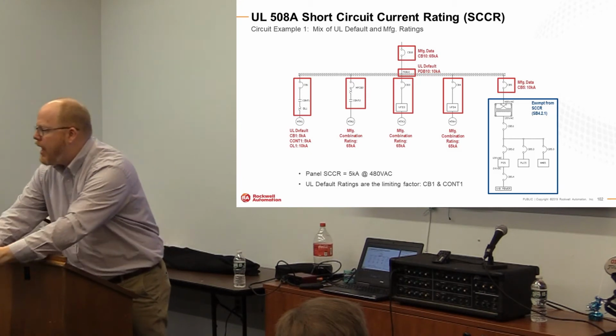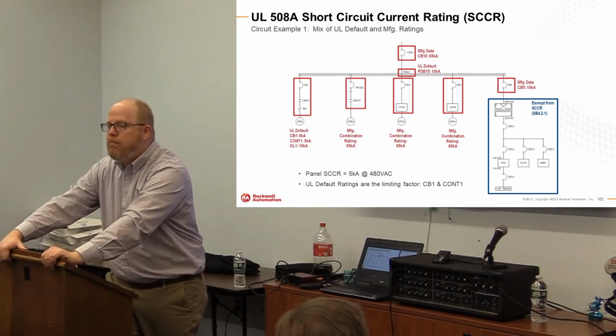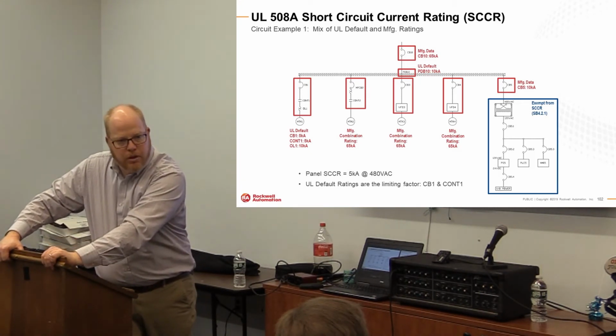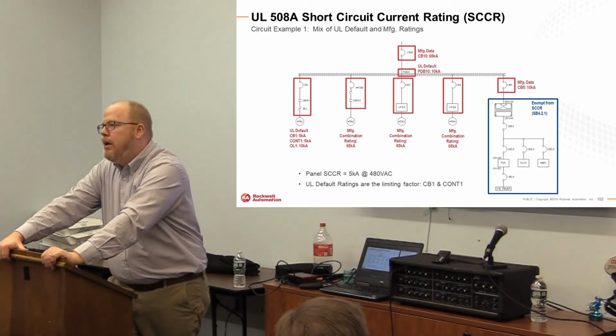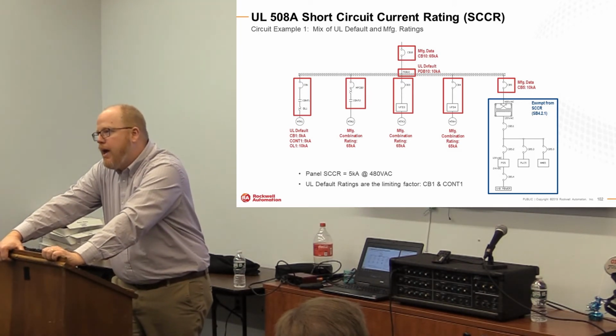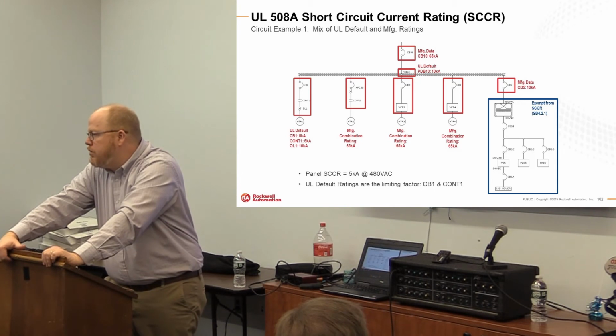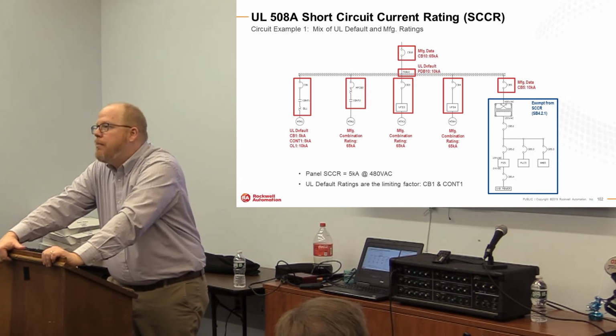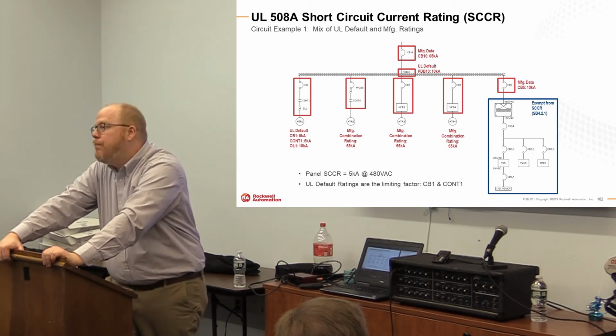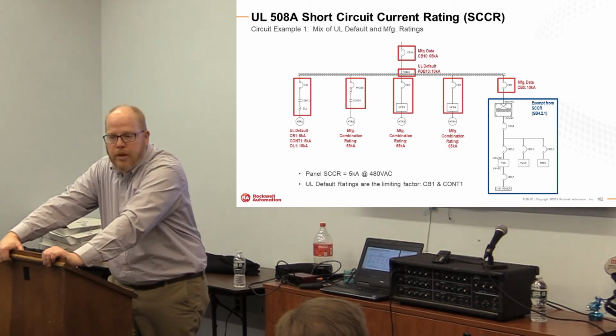So I get asked a lot not only what my rating would be, but what would I do to bolster my current rating? In essence, you would want to swap that guy out to a fully combination rated device. Swap out that breaker that's protecting the transformer.